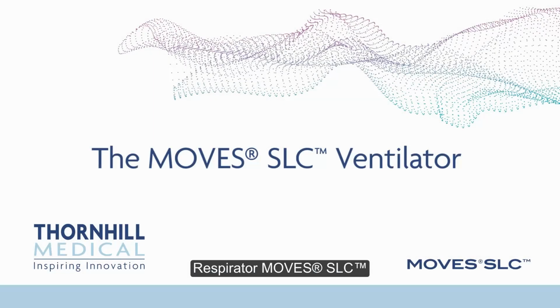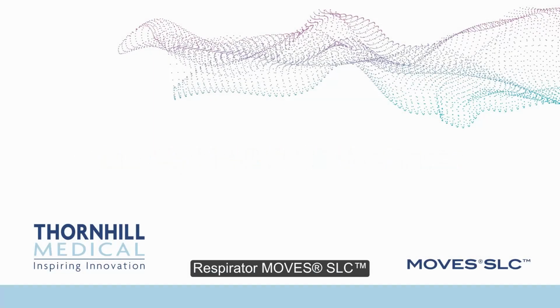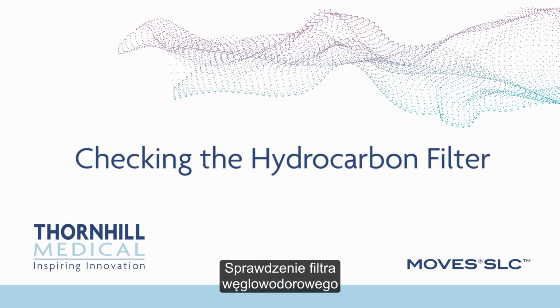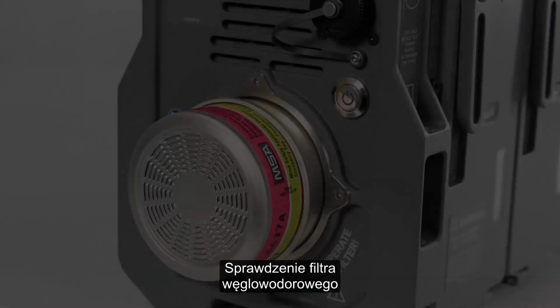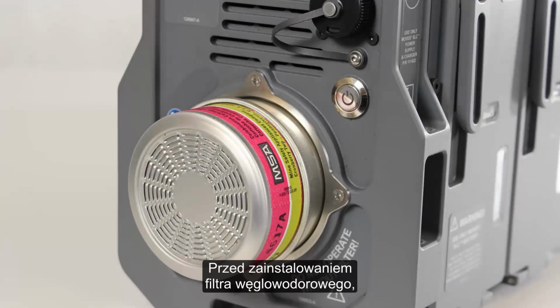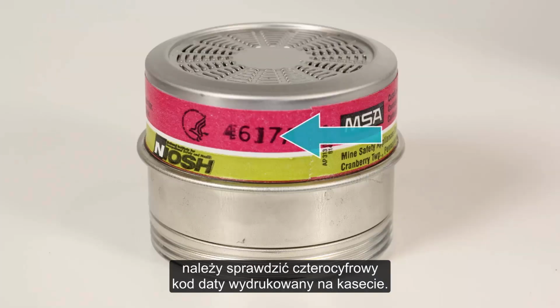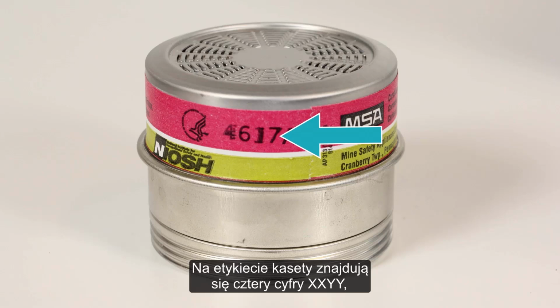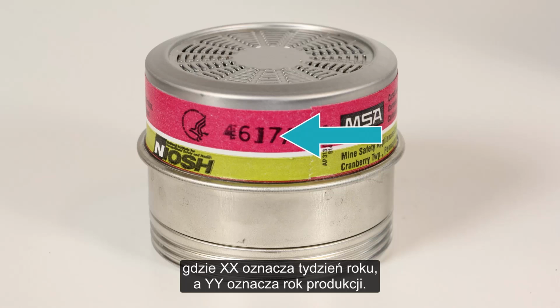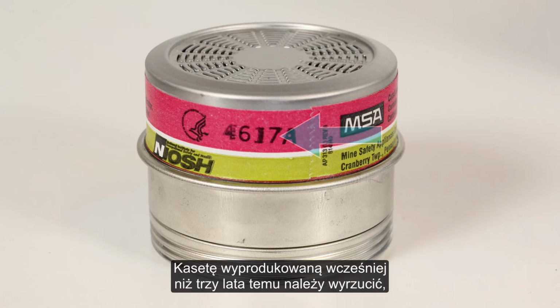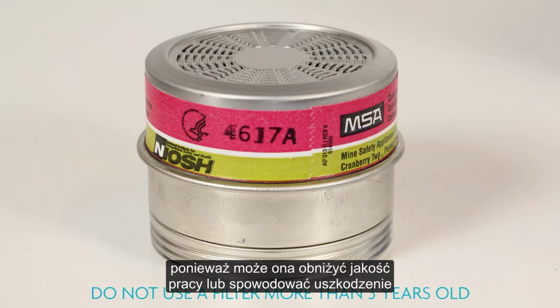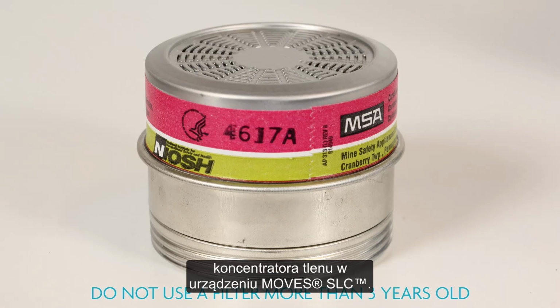The Moves SLC ventilator. Checking the hydrocarbon filter. Before installing a hydrocarbon filter, check the 4-digit date code printed on the cartridge. The cartridge label is stamped with 4 characters, XXYY, where XX is the week of the year and YY is the year of manufacture. A cartridge more than 3 years old should be discarded, since it may degrade performance or cause damage to the Moves SLC oxygen concentrator.